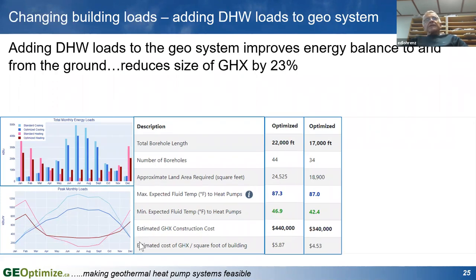The other thing that makes a difference, in this case the thing that was added, a multifamily building and a parking building, is that people in the building are going to have a shower every day and use the laundry and whatever else. They're going to have a certain hot water demand. That water has to be heated. By actually increasing the amount of heating load, what we're doing is changing the energy balance. In this case, that dropped it from 22,000 feet of drilling to about 17,000 feet of drilling. That's pretty significant. You're looking at about $100,000 in cost of the system. That's going to change the economics of the whole system. So you're doing more, you're actually making the system more efficient, and at the same time, you're reducing the capital cost to build it.